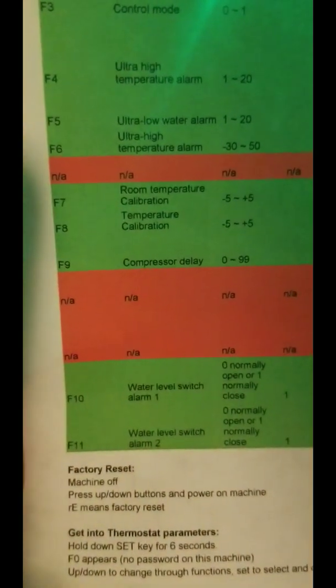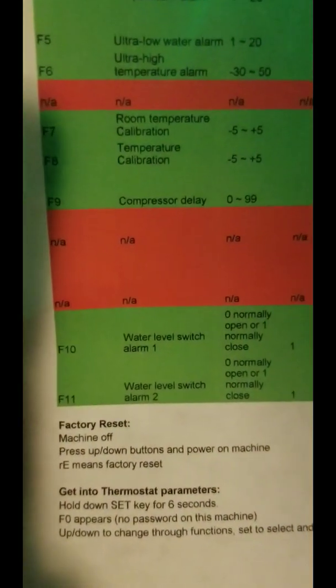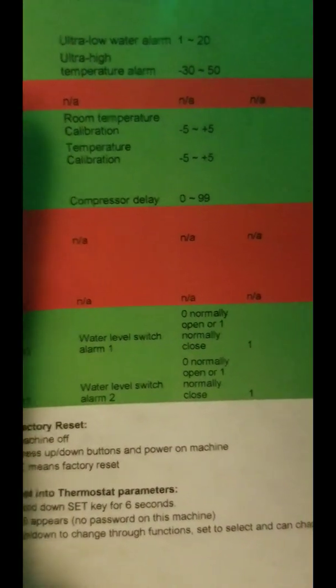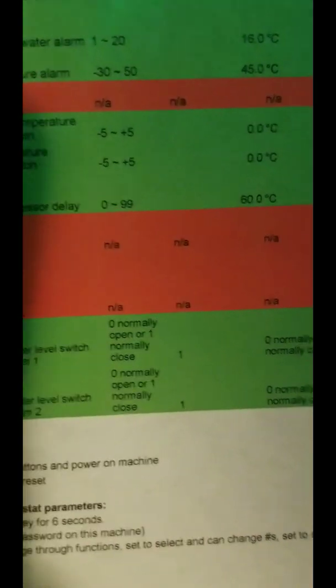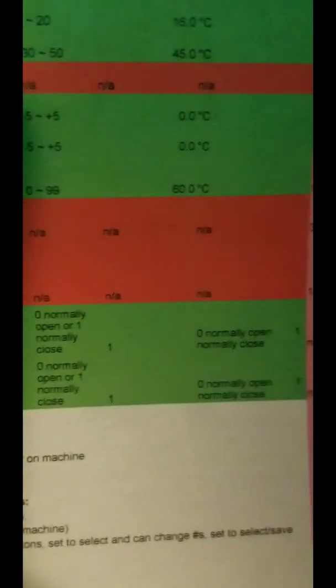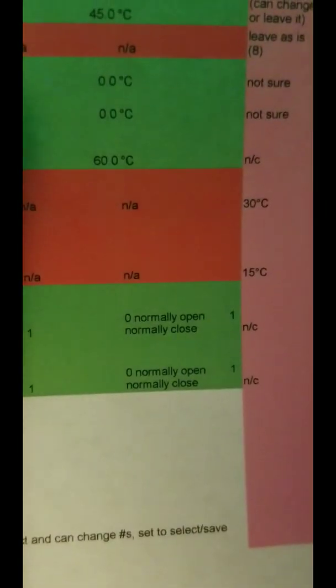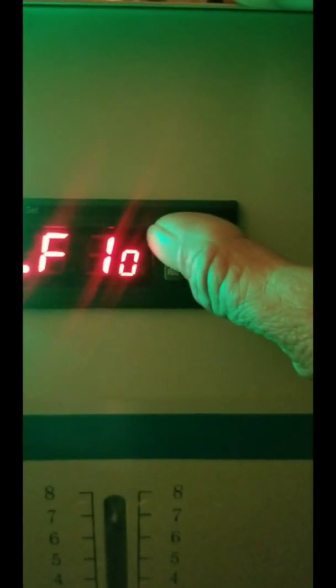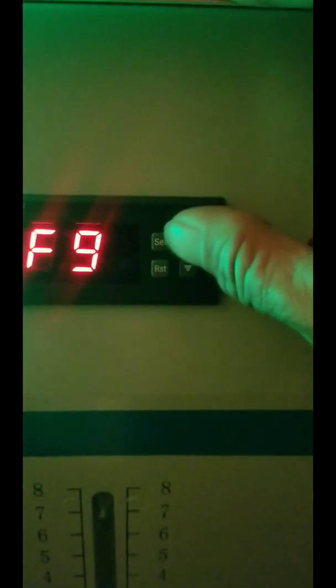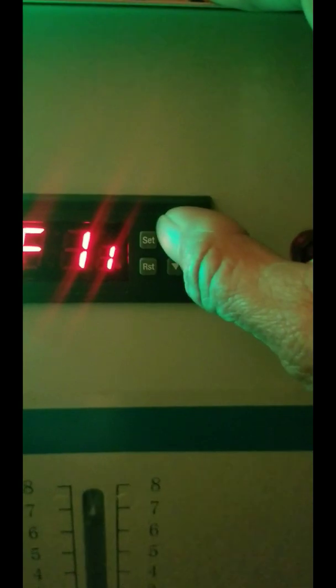This machine also has F10 and F11 — water level switch alarms one and two. Zero is normally open, one is normally closed, and they're supposed to default to one. We'll check the defaults and not change them. F10 does say one, and F11 does say one. So we're going to leave those alone.